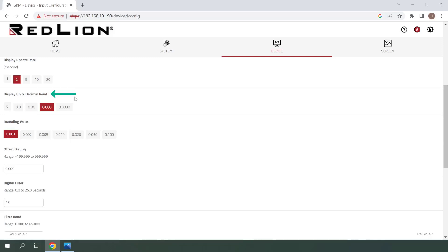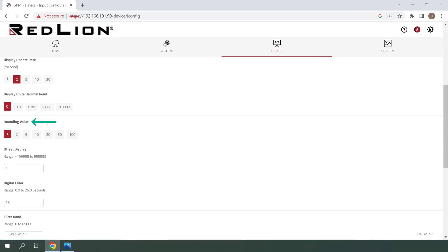Display units decimal point is where we can change the decimal position of the measured value. I'll be changing this to 0 because we just want to display 0 to 100 with no decimal point. Rounding value allows us to round the input reading to the nearest value selected here. I'll leave this at 1 so that no rounding occurs for this demonstration.